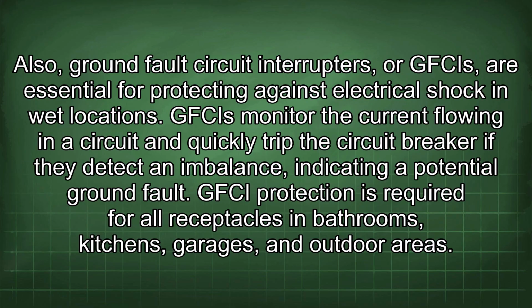Also, ground fault circuit interrupters, or GFCIs, are essential for protecting against electrical shock in wet locations. GFCIs monitor the current flowing in a circuit and quickly trip the circuit breaker if they detect an imbalance, indicating a potential ground fault. GFCI protection is required for all receptacles in bathrooms, kitchens, garages, and outdoor areas.